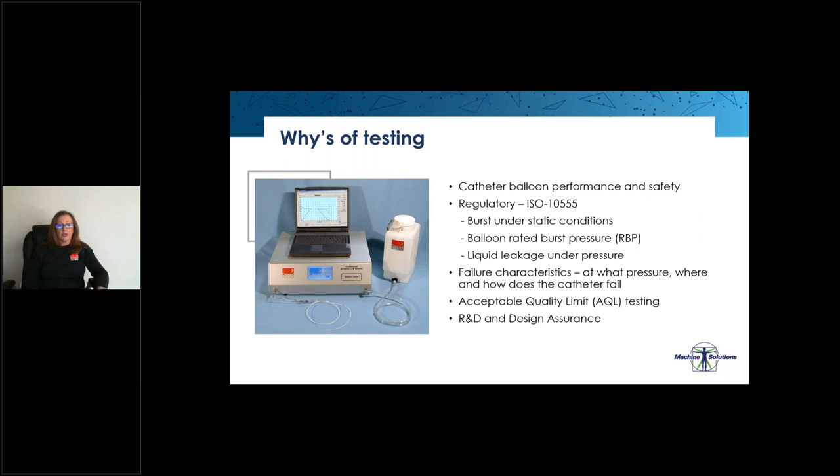In a production environment, acceptable quality limit testing is required. A percentage of every batch of catheters must pass certain test criteria in order for that lot of balloons to be released to market. And we also do testing during the R&D and design assurance phases of developing our balloons and catheters.